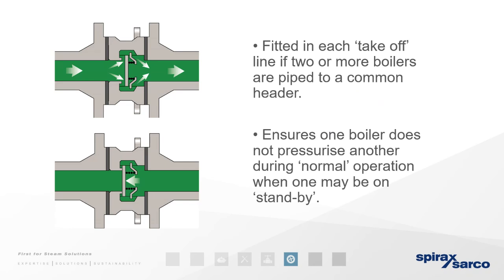And each should be fitted with a check valve. Again, if you have one boiler off and you don't have a check valve, the other boilers would pressurize it. By putting a check valve in there, keeping the isolation, your crown valve and so on, you can make sure that boiler is not wasting steam by being repressurized by the other boilers, but it's also safe to work on because it's been depressurized. It's safe to open.